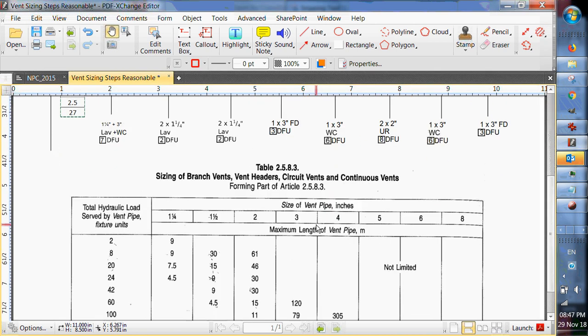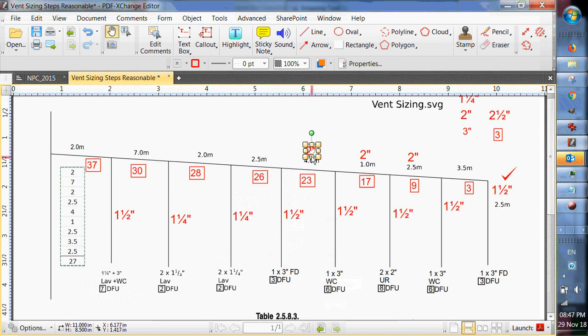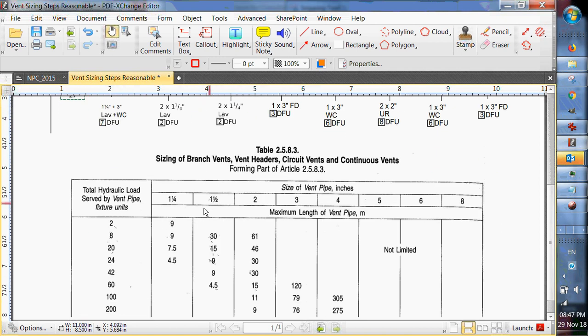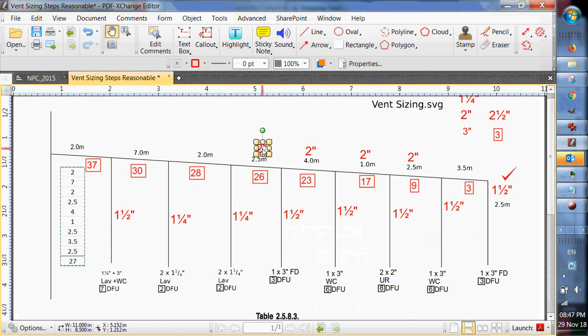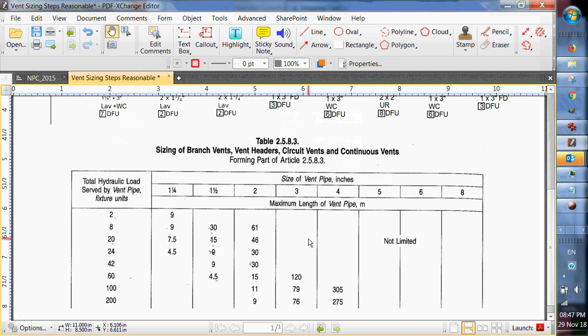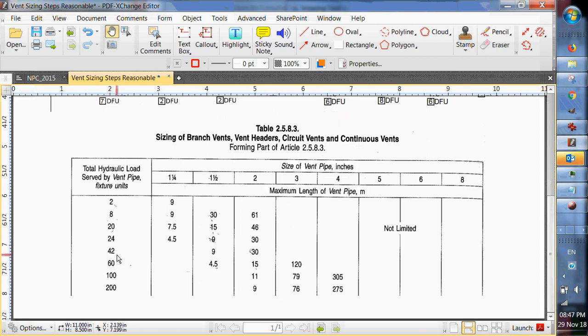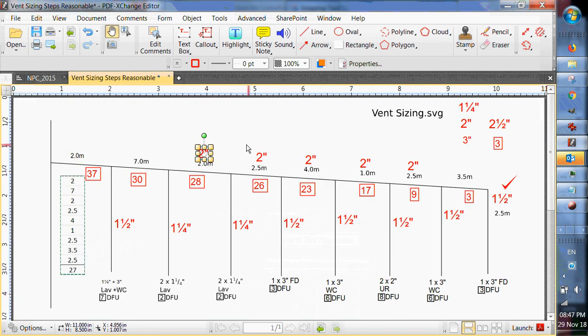Twenty-six fixture units will push us up to this one. Two inch is good for 30 meters. Twenty-eight fixture units. Twenty-eight, so we're still on that one. Thirty meters. Actually, I think it's going to be that way all the way up. Two inch. Yeah, two inch is good up to 42 fixture units. Okay. So those are all two inch.